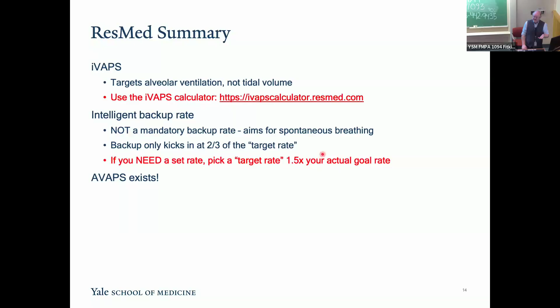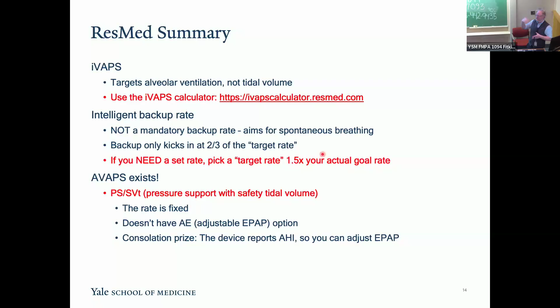AVAPS exists on this, but it's hidden as PSSVT. The rate is fixed. It doesn't have an adjustable EPAP, but one good thing about ResMed devices is that when you get the device download, it actually reports an AHI. And so if you get your download and you see their AHI is elevated, you can do the work of increasing their EPAP until the obstructive events are resolved.